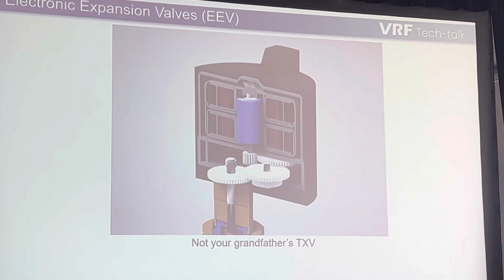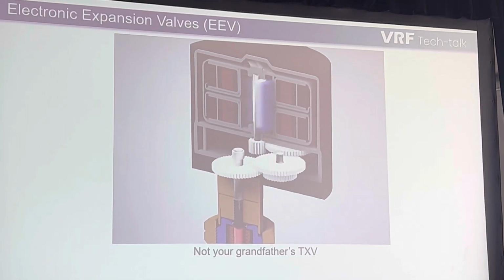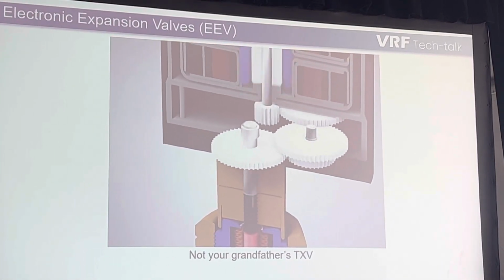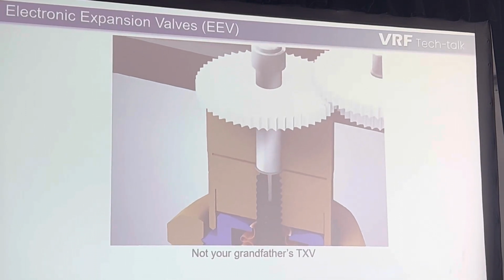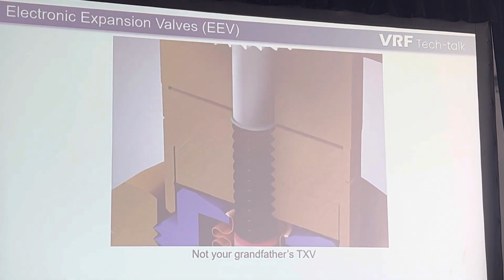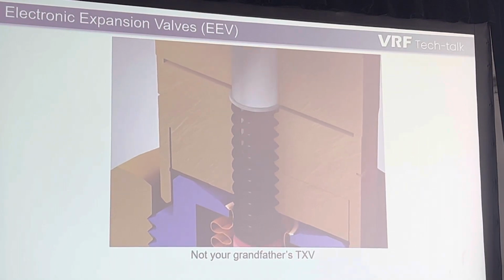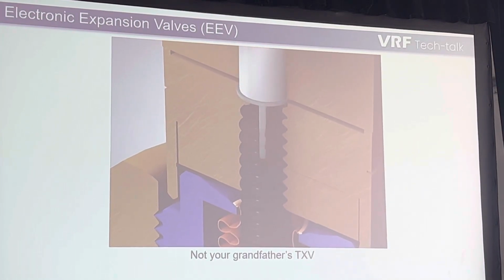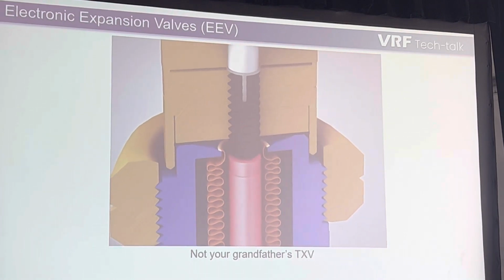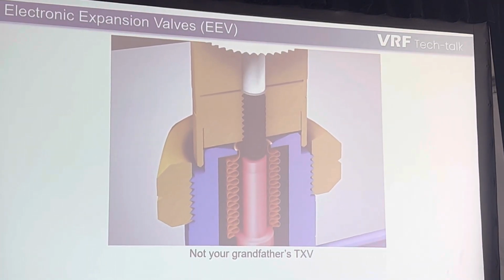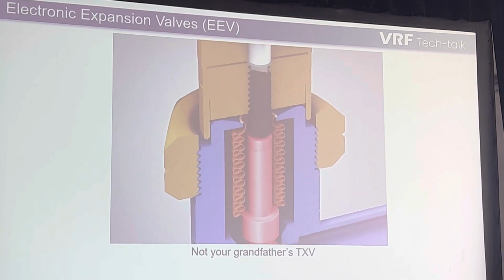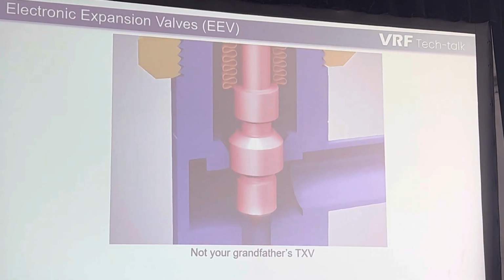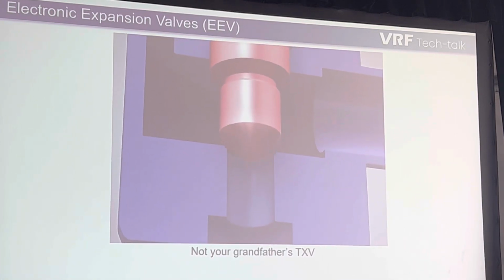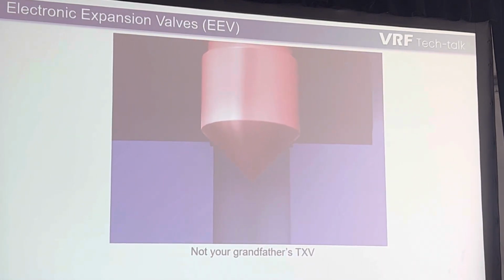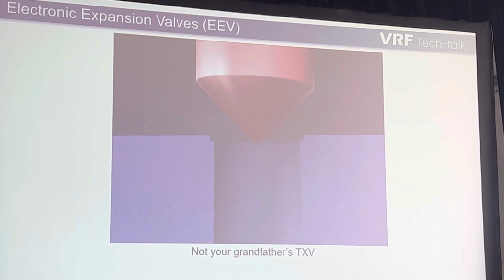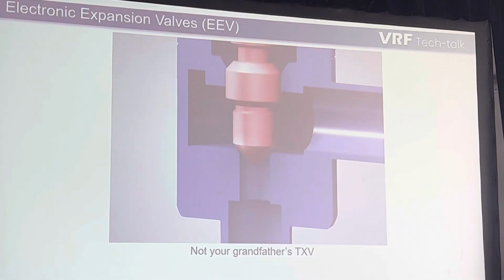This is what is actually happening and occurring inside this valve. And if you've purchased Craig's book or you've attended his class, you'll understand that he's actually got a great diagram, which will also cover a very dumbed down version that I created on the fly to show you exactly how we drive that expansion valve electronically. But this is essentially what we're doing. It drives down, closes off refrigerant flow, it opens up. That means that if you pull this valve off, it is going to open full open. A lot of people have a misconception that when they pull this valve head off on VRF equipment, that it's closed the valve. It does not. You have now just created it to 100% open and allowed the flow to pass through unrestricted.